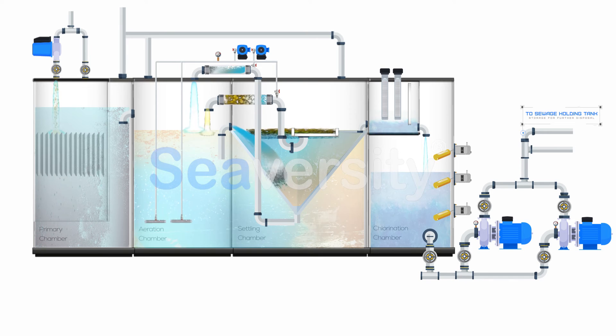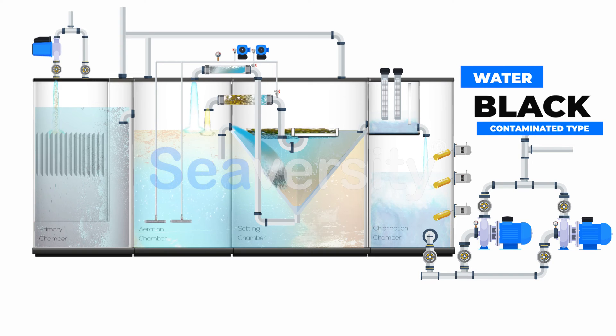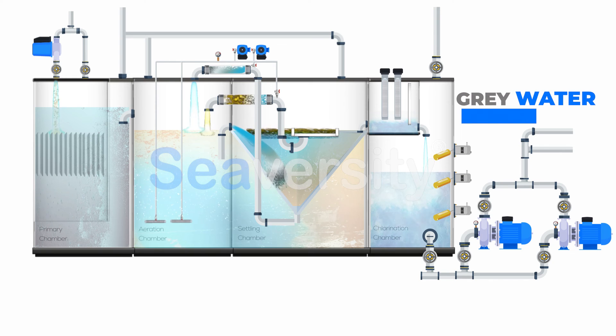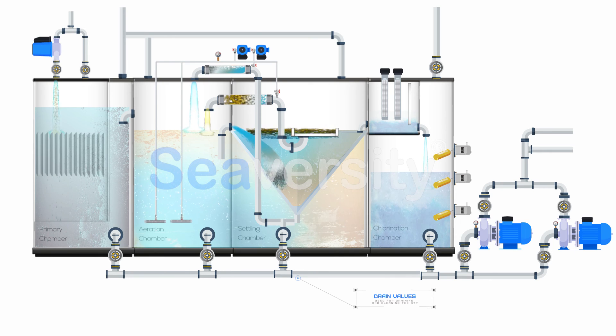Based on our previous discussion of wastewater management, we've differentiated between two main types of wastewater: black water and grey water. Black water is the more contaminated type, coming from toilets, urinals, hospital waste units and scuppers, as well as drainage from cargo holds that transport live animals. Grey water comprises drainage from dishwashers, cabin showers, laundry, and air conditioner condensates. Unlike black water, grey water bypasses the primary treatment chamber and is directed straight to the chlorination chamber. To facilitate regular maintenance, drain valves are installed within the system, allowing for the draining and cleaning of the treatment chambers, preventing accumulation of sediments or blockages that could impair the system's efficiency.